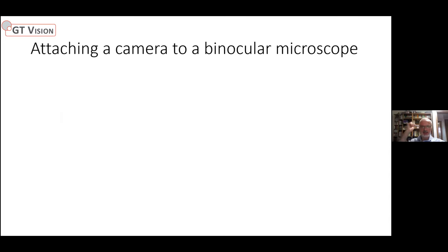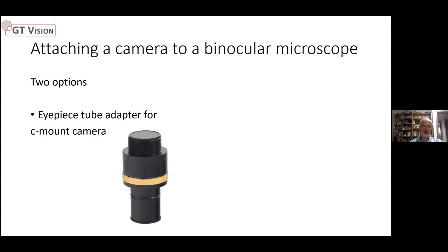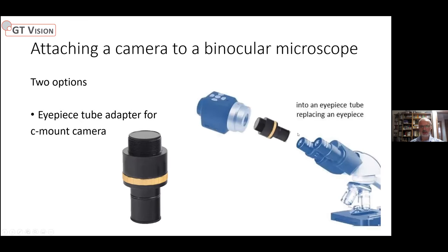If you've got a binocular microscope, you don't have a trinocular port, but there are still ways to attach a camera. There are two options: first, using an eyepiece camera — you take your eyepiece out, plug the eyepiece camera in, and it connects to a PC via USB. The other option is using an eyepiece tube adapter for a c-mount camera, where you attach the c-mount adapter and plug it into the eyepiece. This is more versatile because you have a better choice of cameras and a range of magnifications to suit your sensor size.